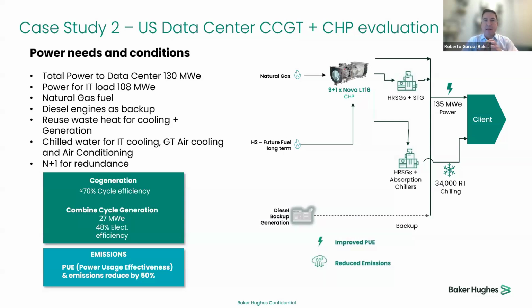Knowing that the grid is not going to be available for a long time, the gas turbines will run on natural gas at the beginning, and when hydrogen is available at the site and feasible to use, the turbines can take it. The design of our Nova LT16 turbine can use hydrogen without any modification, up to 20% hydrogen. If more hydrogen is required, it can be done with some modifications to the turbine. This is the long-term plan this data center has for reducing emissions.